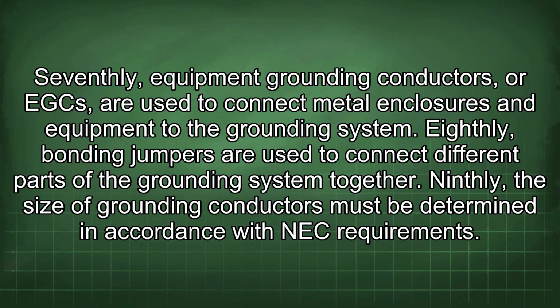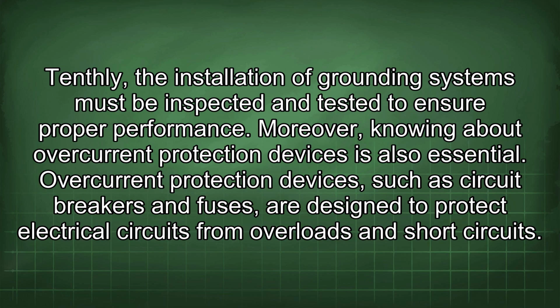Eighthly, bonding jumpers are used to connect different parts of the grounding system together. Ninthly, the size of grounding conductors must be determined in accordance with NEC requirements. Tenthly, the installation of grounding systems must be inspected and tested to ensure proper performance.